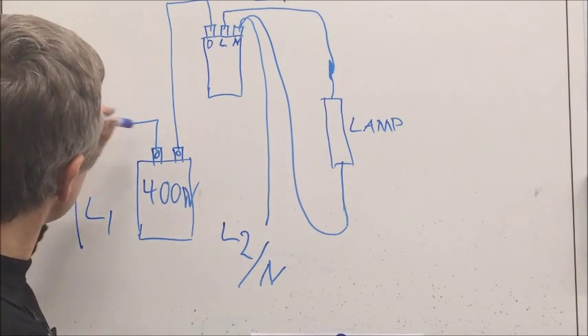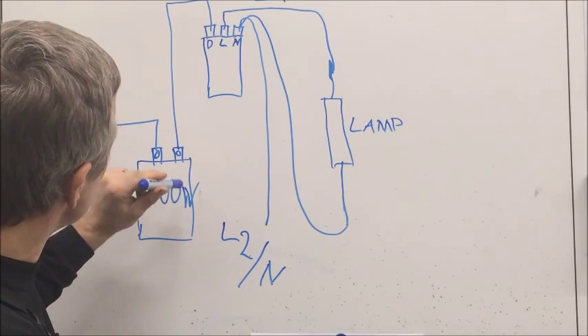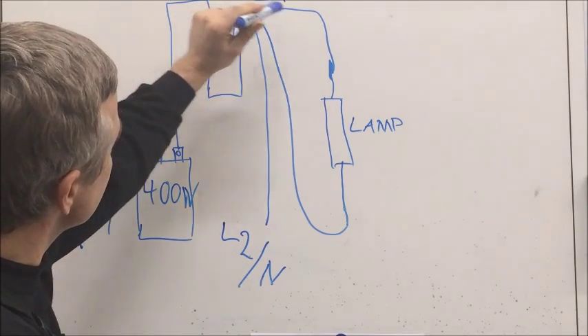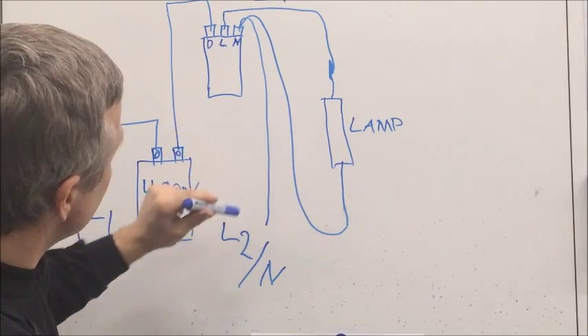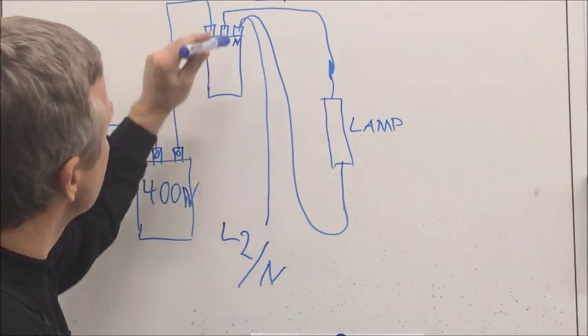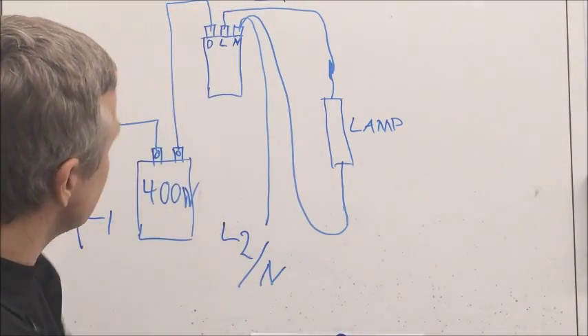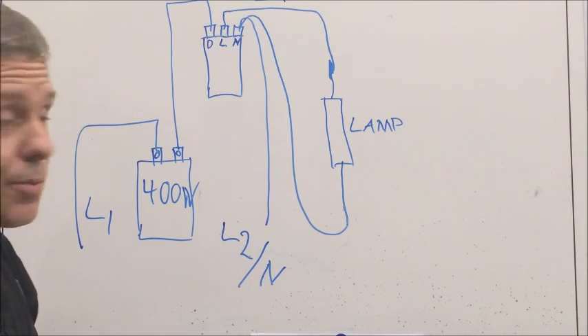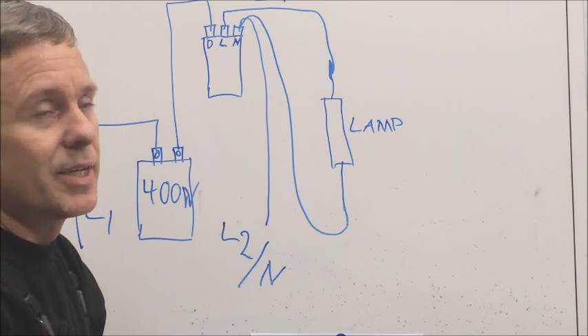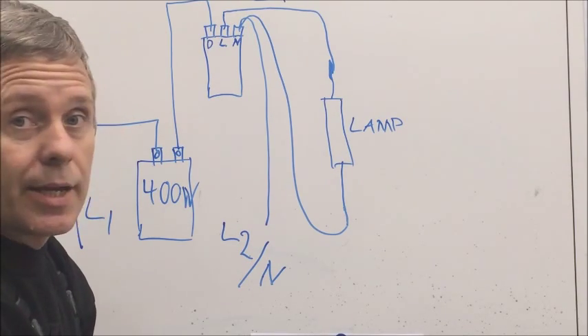So, let's just quickly run through it. It's L1 in here, the power goes in through the ballast, and boom, up into the igniter, out on the middle leg, to the lamp, and then the neutral, or the opposing leg, L2, is connected between both the lamp and that side of the igniter. So, this was with a fixed ballast of 400 watts. That means that we cannot regulate it, it's just the way it is at all times.